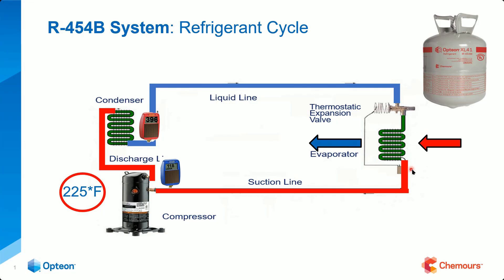As it picked up that superheat — this bulb is filled with refrigerant. Most of the time it's the same refrigerant that's inside the system, but not always, and it doesn't interact with the refrigerant in the system. Another pressure-temperature relationship: it expands when it gets warmer, higher superheat, pushes pressure down on the diaphragm and gives it more flow, allowing more liquid until it gets satisfied and then it adjusts itself. That's the cool thing about a TXV system.